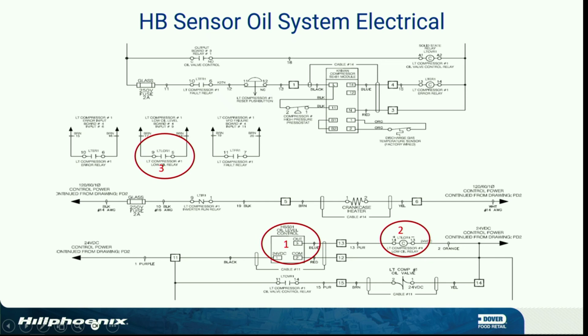All right, so we're going to energize our 24 volt cube relay. That's going to make our input again to our PWM flex combiner for LT1. And that's going to start our pulse count of 5 seconds on, 55 seconds off. And the reason we did that with low temp is because that's a lot of pressure from 515 to 200 PSI. So we don't want to dump all that pressure in there and overload the suction on the low temp. That again makes a board output from the flex combiner, which turns on our solid state relay, which pulses our solenoid. All right?